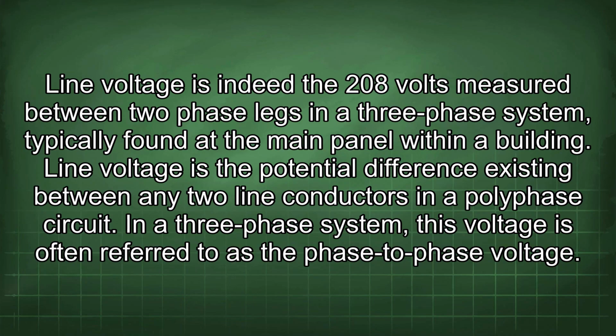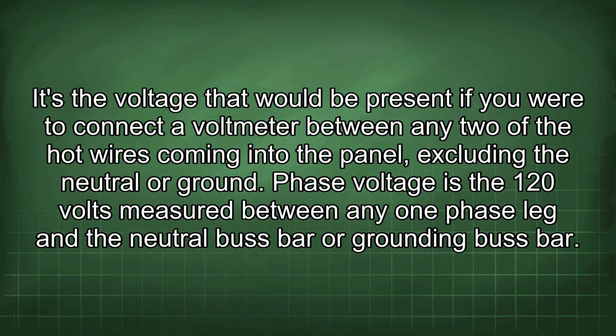Line voltage is indeed the 208 volts measured between two phase legs in a three-phase system typically found at the main panel within a building. Line voltage is the potential difference existing between any two line conductors in a polyphase circuit. In a three-phase system, this voltage is often referred to as the phase-to-phase voltage. It's the voltage that would be present if you were to connect a voltmeter between any two of the hot wires coming into the panel, excluding the neutral or ground.